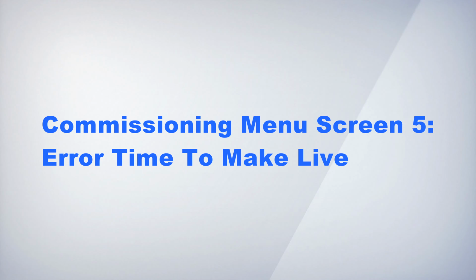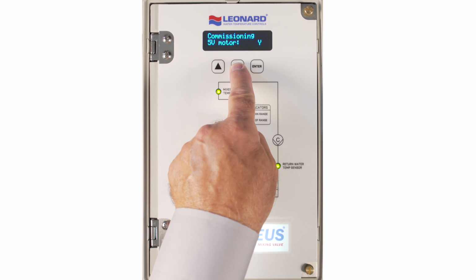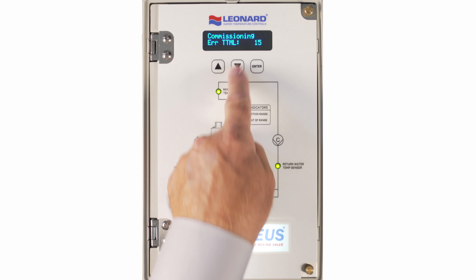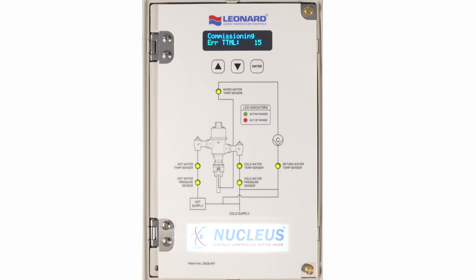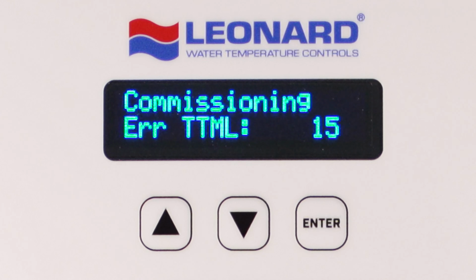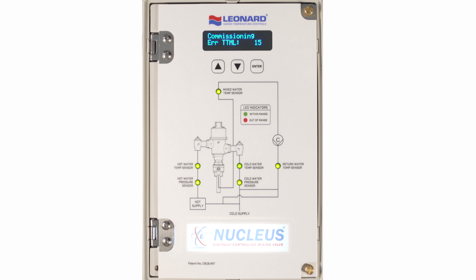Commissioning menu screen 5, error time to make live. Pressing down 4 times displays error TTML. This indicates the time to make live, which is an elapsed time in seconds as to when an actual error will be identified by the processor and then subsequently recognized as a true error and displayed on the LCD screen.